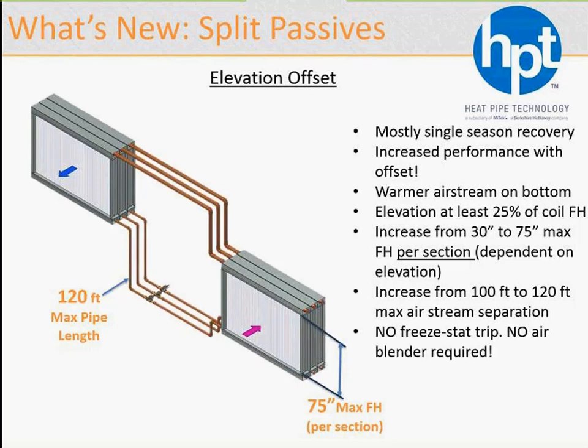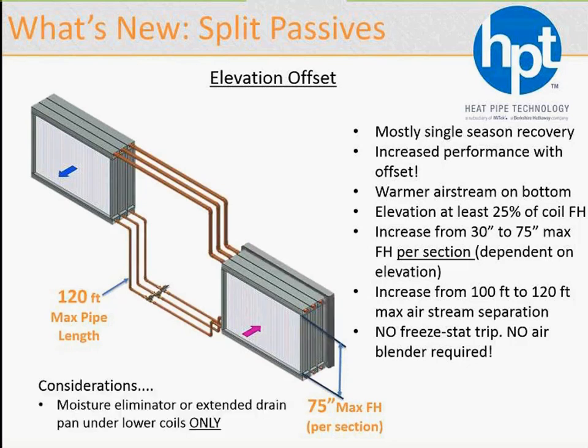Will you need air blenders here? No, you do not. The temperature profile across the supply side is fairly uniform, so no air blenders are required. However, you still need a moisture eliminator or an extended drain pan on the warm side or the lower side of this heat exchanger.